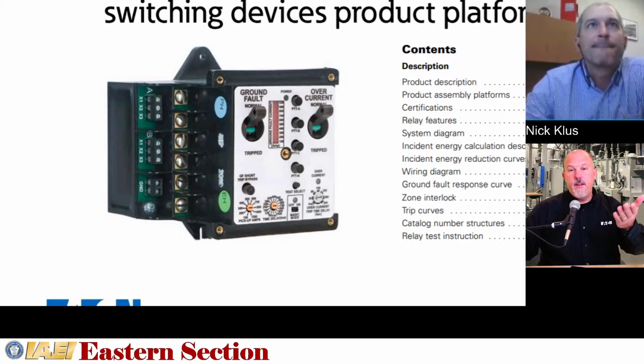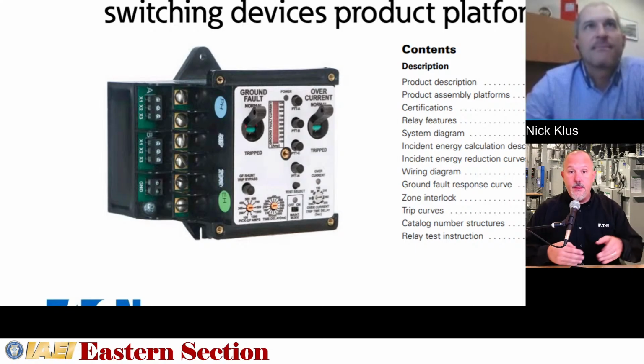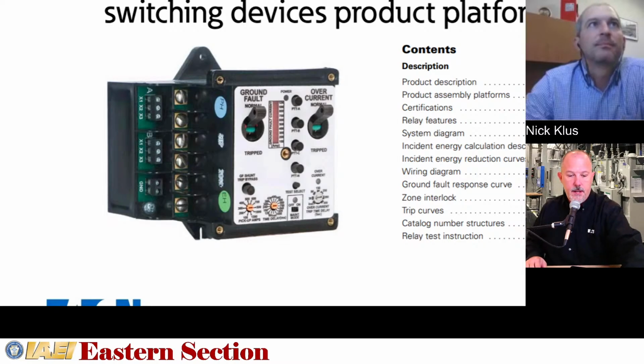A good point. Since it's ground fault protection, we have to coordinate ground fault protection, and there's a trip curve associated with that. The adjustments on that will let you move that curve around within the requirements of the NEC for 1000 amps and above. You can only go up to 1200 amps and a 2-second delay, etc. But like you say, that's very adjustable, and you can apply the arc just like the breaker guys. Let me get Manny back on here. Manny, how low can I apply an arc reduction maintenance switch on the breaker frame ratings?